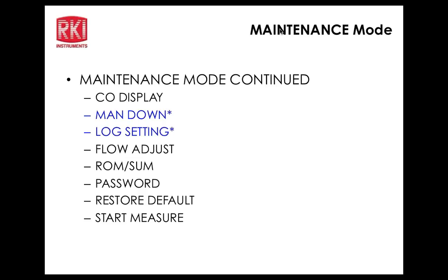That would give you a better setting. The problem with blocking the flow is now you've got the most insensitive setting for low flow, so you could have a pretty low flow that you wouldn't realize unless you actually looked at it with a flow meter. It's better to have it a little bit above the absolute no-flow from a safety standpoint.